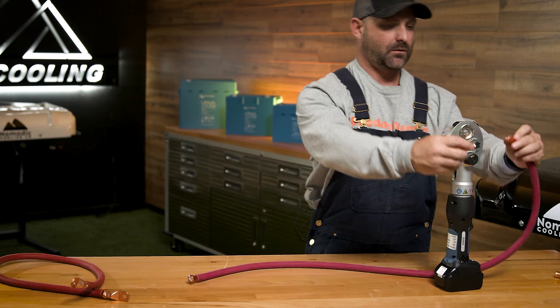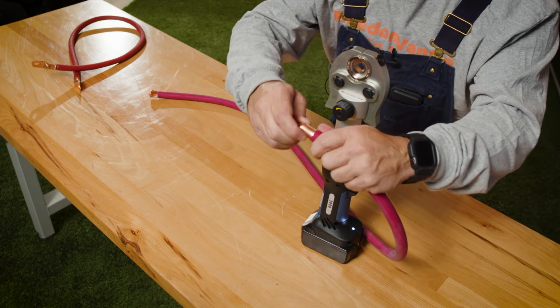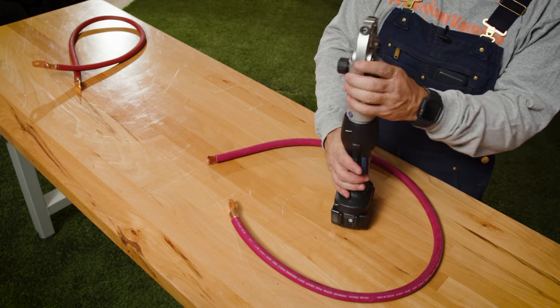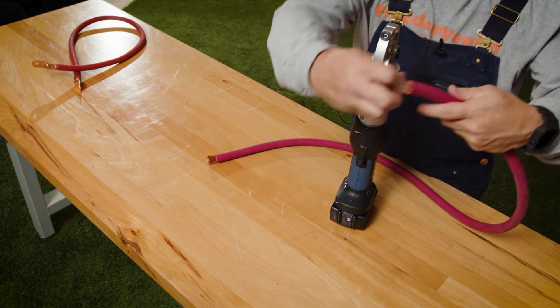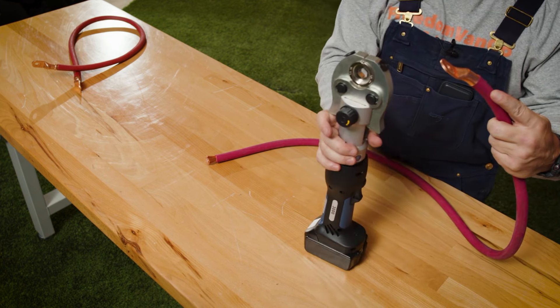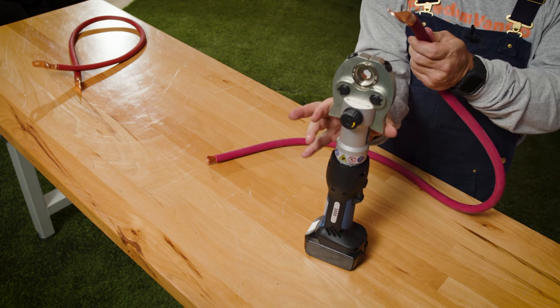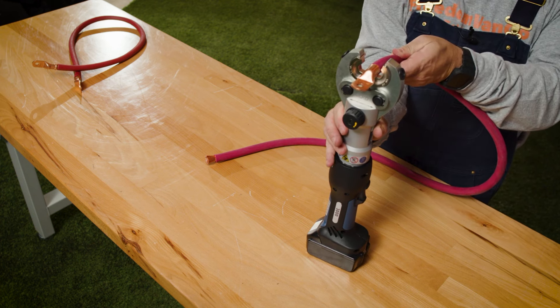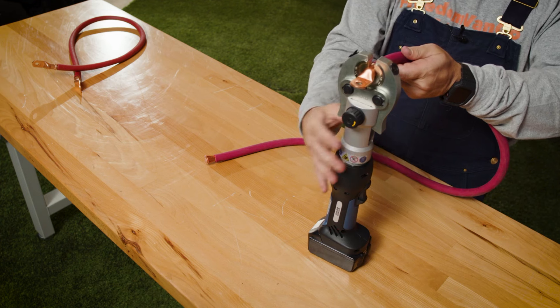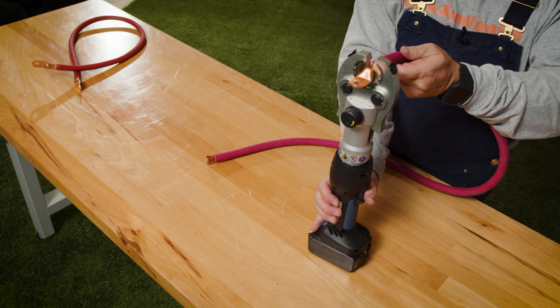I'm going to insert my four-aught cables — my lugs into the wire. I've got my size 95 die in here. I've got my 4/0 wire, my 4/0 lugs. I'm going to squeeze these two together — by squeezing it together, it opens up the flange. I'm then going to crimp right down in the middle on this four-aught. Make sure everything's centered. Once I do that, I'm going to press down on the trigger. Let's go.